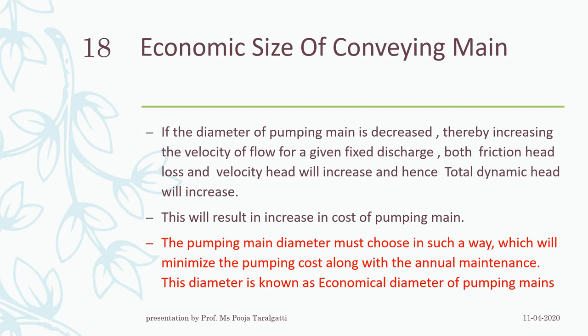If the diameter of the pumping main — that is, the pumping pipeline — is decreased, it increases the velocity of flow. For even a fixed discharge, both the friction head and the velocity head will increase, and hence the total dynamic head will increase. We keep on reducing the diameter to get more pressure at the consumer end, but at a certain level decreasing the diameter increases losses and velocity head, so total head increases. You can't just keep reducing the diameter to achieve a certain pressure.